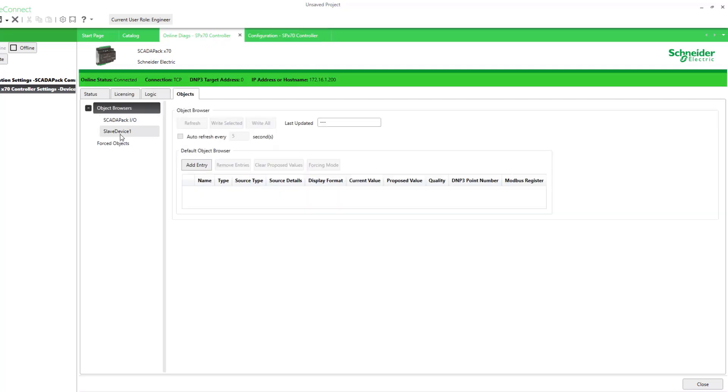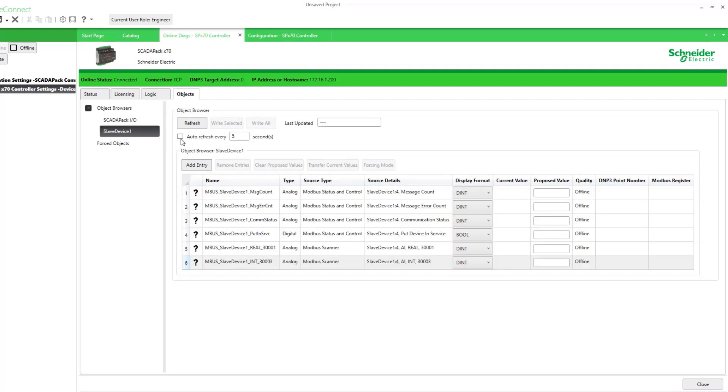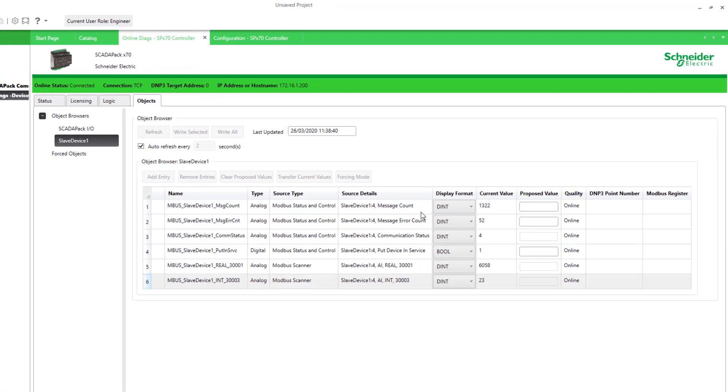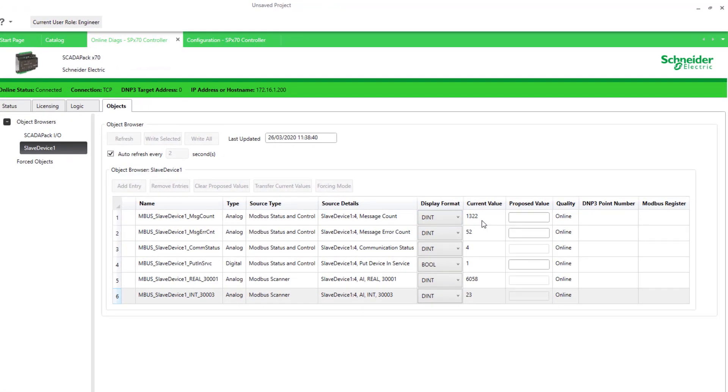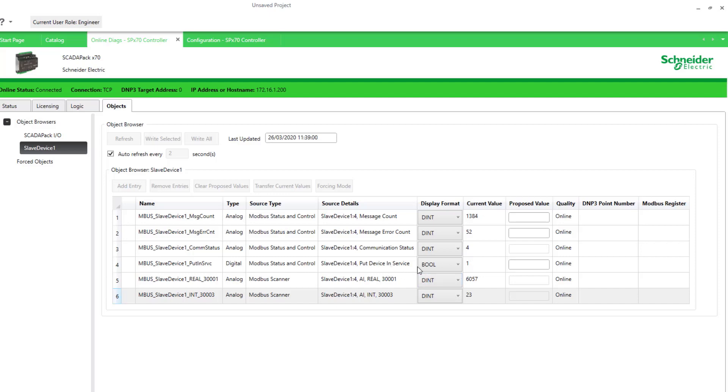Here's our browser added and then start refreshing. Let's look at it a little more often, perhaps every two seconds. We see the message count increasing. It's supposed to be polling twice a second. So we see that increasing. There's been some error messages. This is before I connected the cable. And then we have a communication status of four. We'll look up what that means, but I assume that is successful. You can take the device in and out of service with this point. And then here's our pressure.